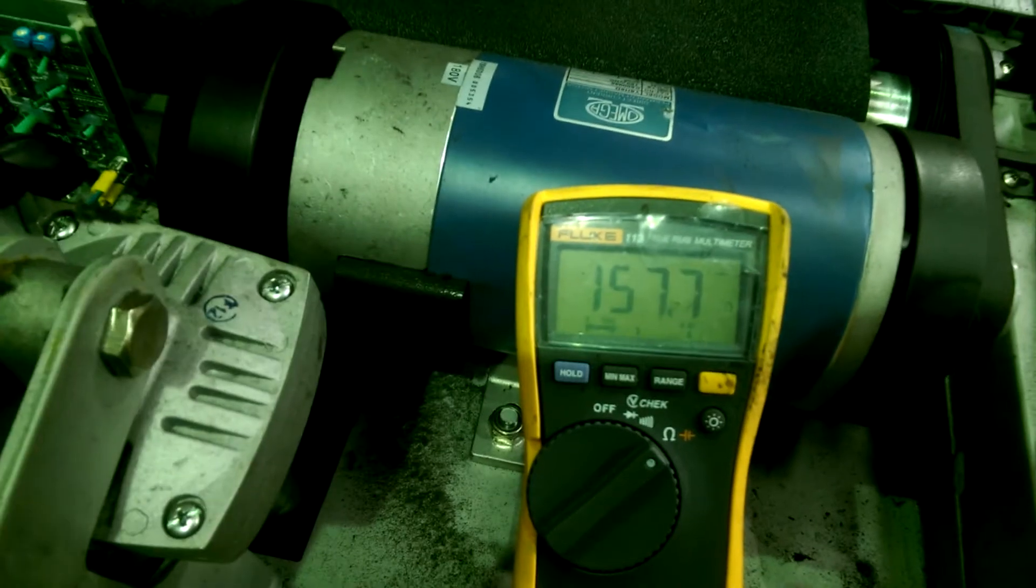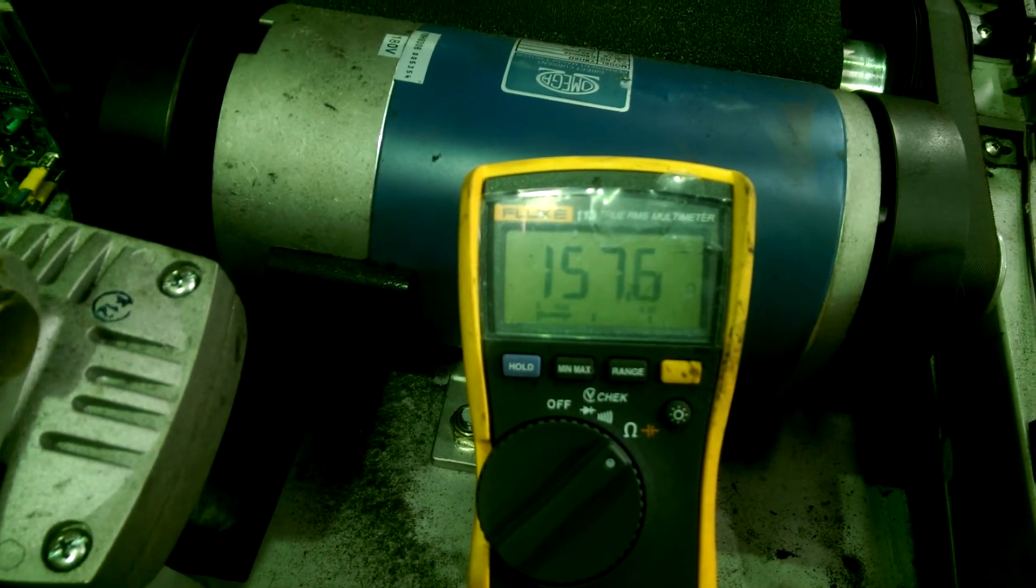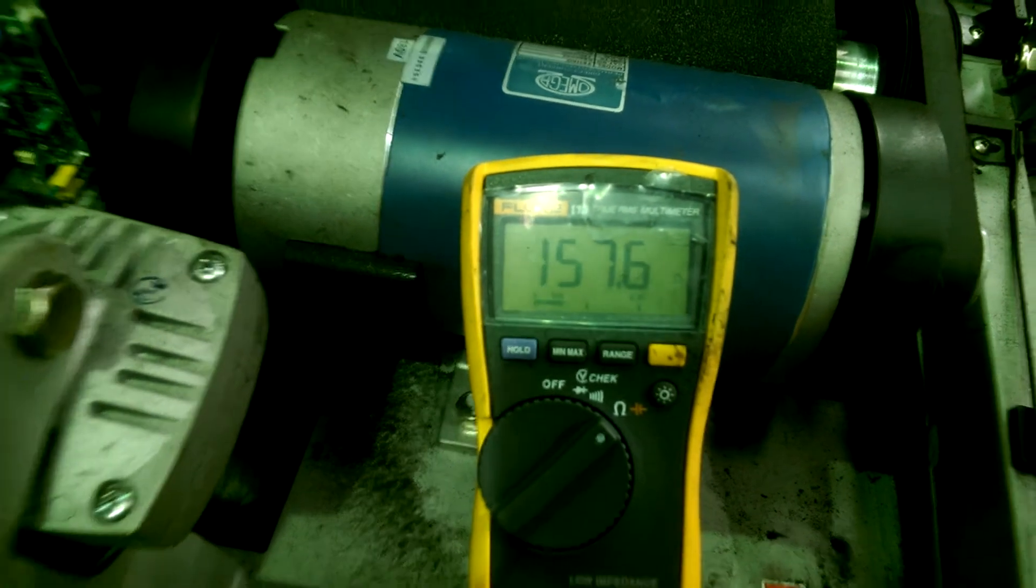We can test the windings to earth. So I'm going to put one probe on a good earth, which for example is there, and the other one on one of the parts of the windings. And this should be a really high resistance. It should be open circuit. And we're actually measuring 157.8 ohms, which is in the scheme of things really quite low.